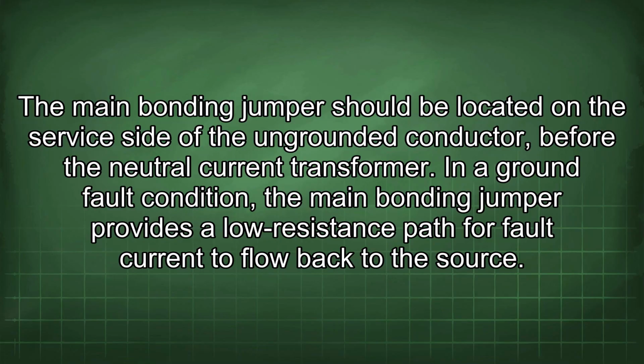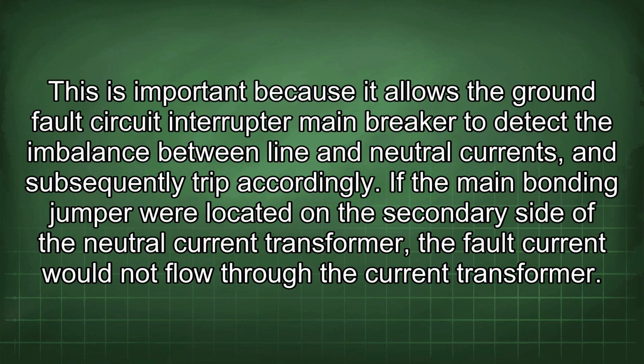The main bonding jumper should be located on the service side of the ungrounded conductor before the neutral current transformer. In a ground fault condition, the main bonding jumper provides a low resistance path for fault current to flow back to the source. This is important because it allows the ground fault circuit interrupter main breaker to detect the imbalance between line and neutral currents and subsequently trip accordingly.